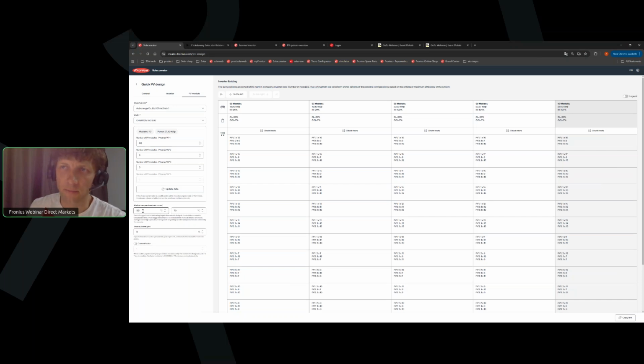Here you can find the minimum module temperature. Because we are a little bit in the north, this winter is quite cold, so I recommend inserting a bigger number, for example -30, just to be sure if you plan PV modules near 1000 volts that you are in a safe way - better to write a lower degree.